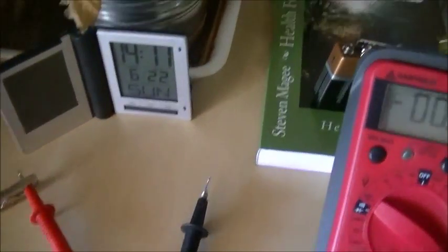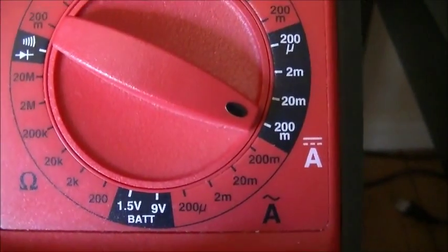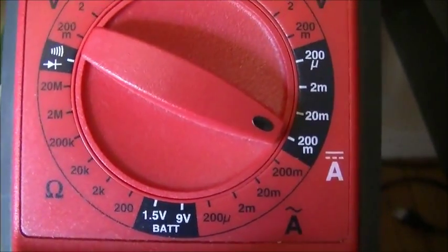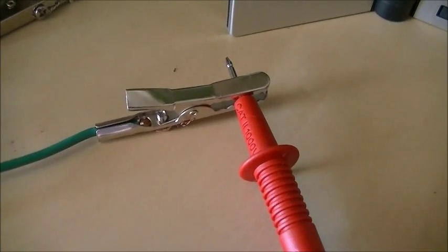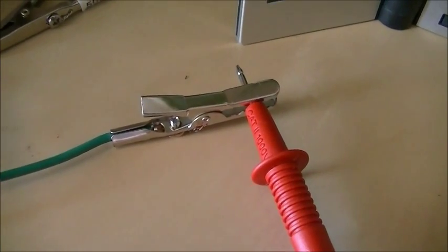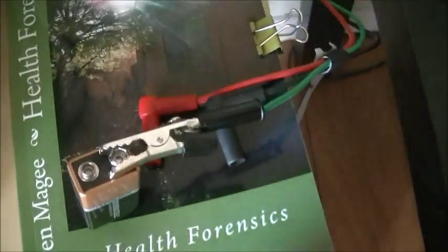We have another circuit here with our meter again set on 200 milliamps on DC amps. Our probe is going out to an 8 foot ground rod in the back garden that's non-electrified, and our battery is connected into the electrical grounding system.